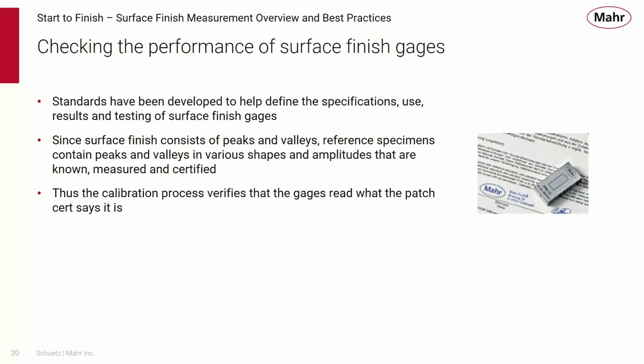Now, how do you check the performance of a surface finish gauge? Well, standards have been developed to help define the specifications, use, results, and testing of surface finish gauges. Since surface finish consists of peaks and valleys, reference specimens contain peaks and valleys in various shapes and amplitudes that are known, measured, and certified. Thus, the calibration process verifies that the gauge reads what the patch cert says it is.